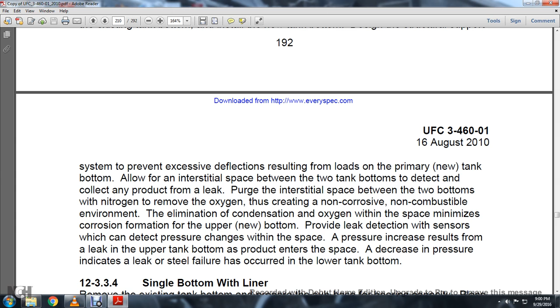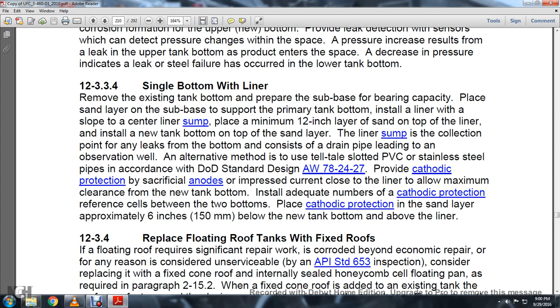Provide the same liner with a sump for collection points of leaks at the bottom, consisting of a drain pipe leading to the observation well. An alternate method is telltale slotted PVC or stainless steel pipe according to Department of Defense Standard Design AW 78-24-27. Provide cathodic protection, sacrificial anodes or impressed current, close to the liner with maximum clearance for the new tank bottoms. Install an adequate number of cathodic protection reference cells between the two bottoms in the sand layer, approximately 6 inches below the tank bottom above the liner.